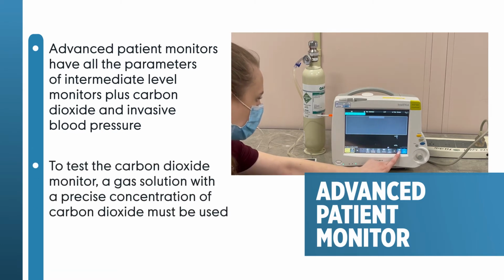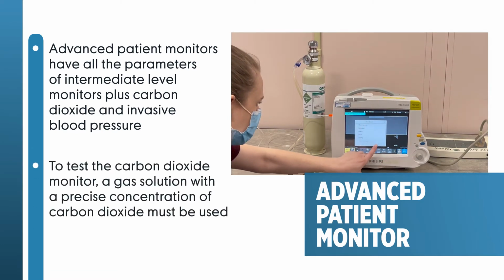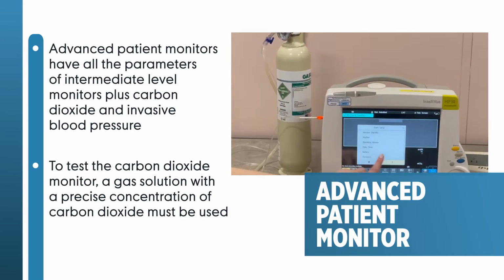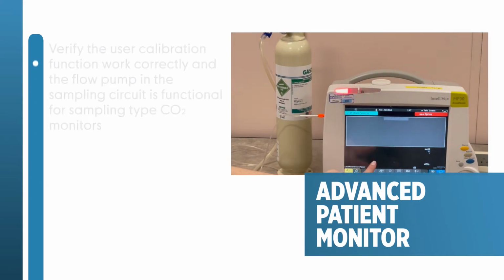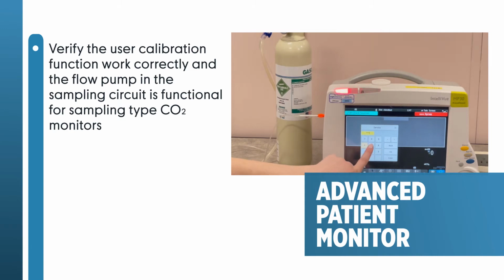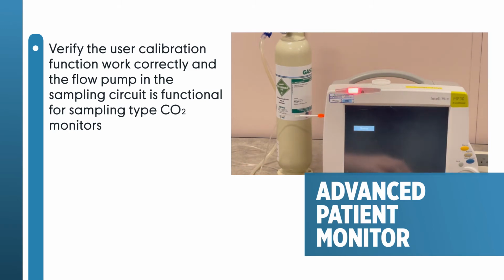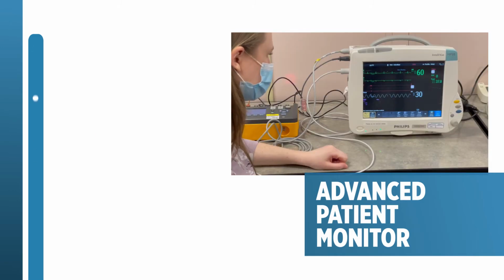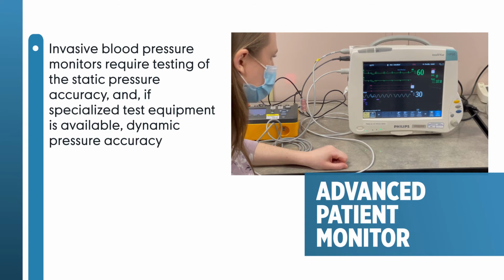To test the carbon dioxide monitor, a gas solution with a precise concentration of carbon dioxide must be used. Verify the user calibration function works correctly and the flow pump in the sampling circuit is functional for sampling type carbon dioxide monitors. Invasive blood pressure monitors require testing of the static pressure accuracy and, if specialized test equipment is available, dynamic pressure accuracy. Now you are ready to test the alarms on the patient monitor.